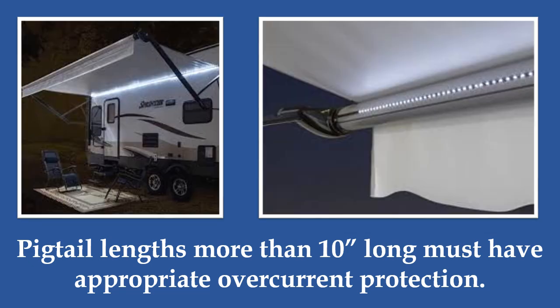For example, recent advancements in lighting have brought on a wide variety of LED lighting which needs to be noted, along with standard lighting that have pigtail connections in excess of 10 inches in length. In particular are the use of LED strip lights that are built into or associated with awnings as seen here. Some of these pigtails that provide connection to the RV's low voltage system are in excess of 6 feet in length and are fitted with 18 gauge wire or smaller.